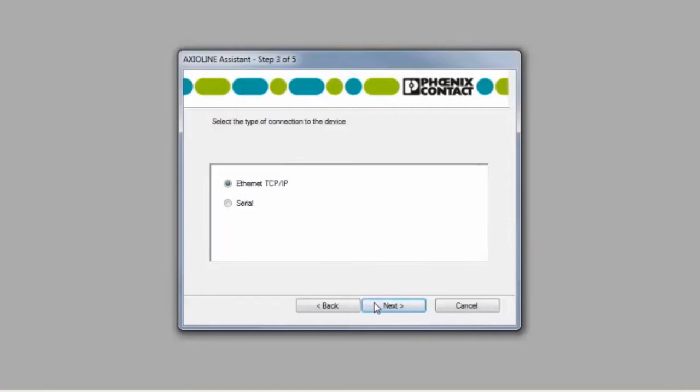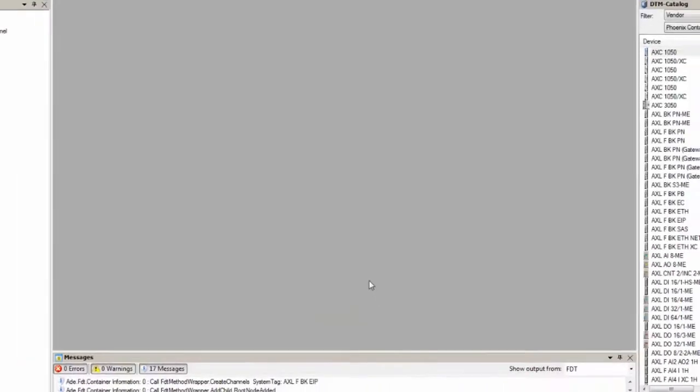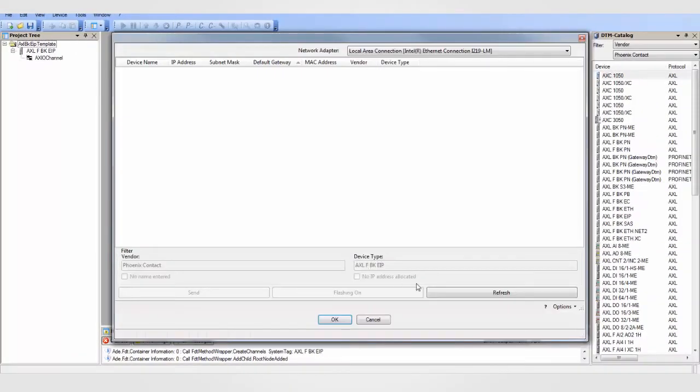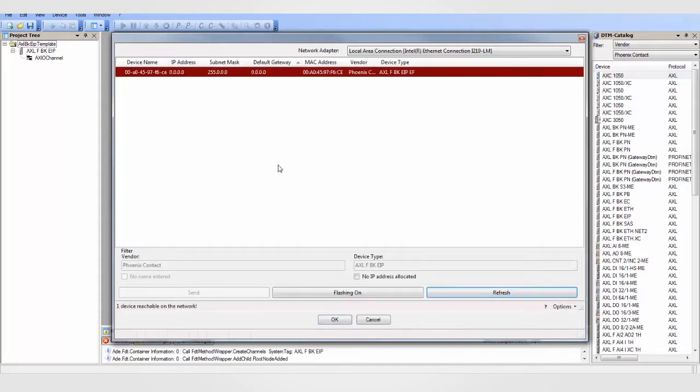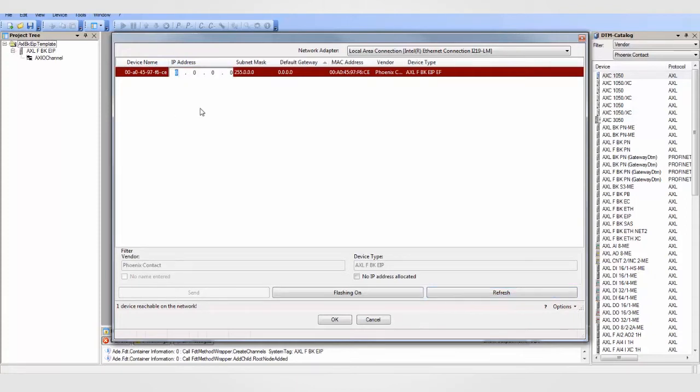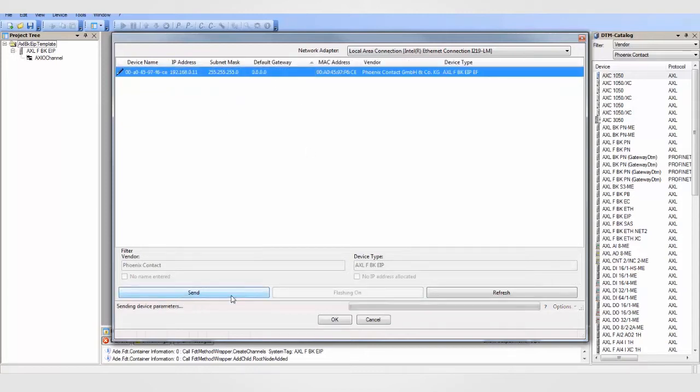Now choose how you are connecting to the bus coupler and whether you need to scan for the device or already know its IP address. From this page, click the Refresh button so that the software will scan the network for bus couplers. Once the BK appears, double-click on the line and enter an IP and subnet for this station. When complete, click the Send button to make your setting permanent.